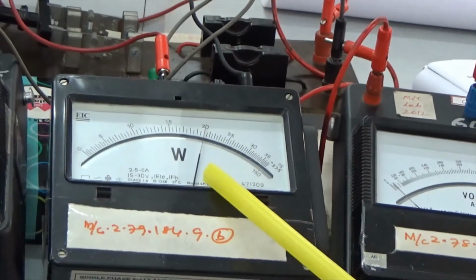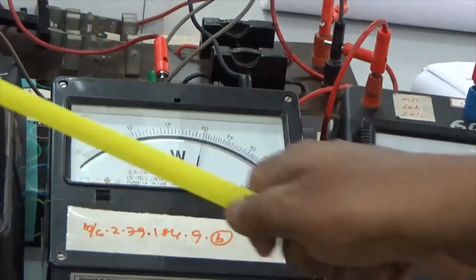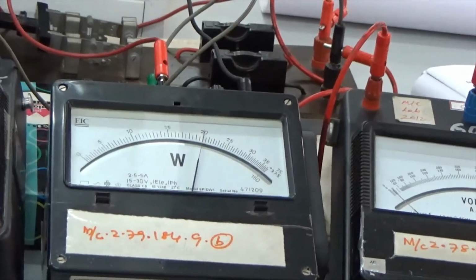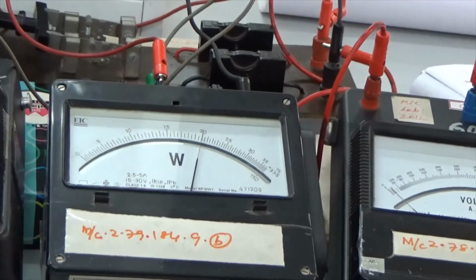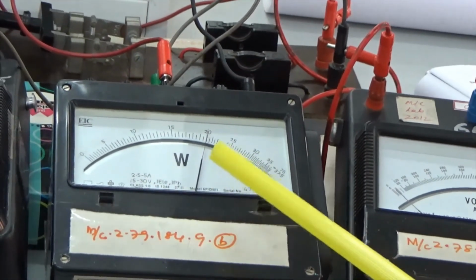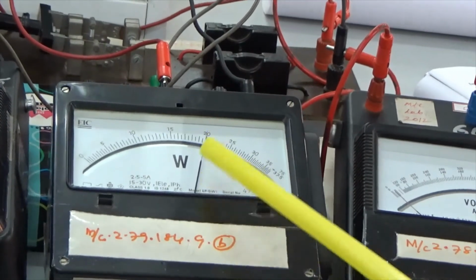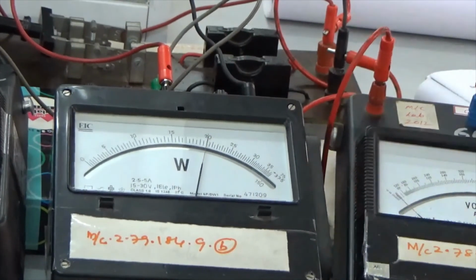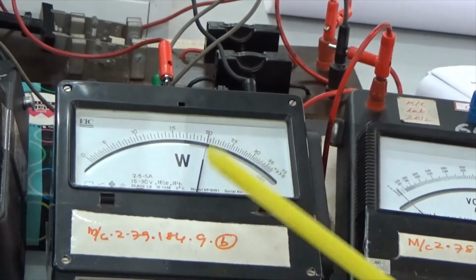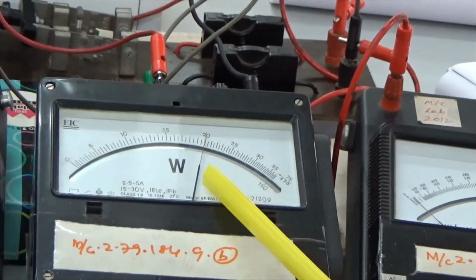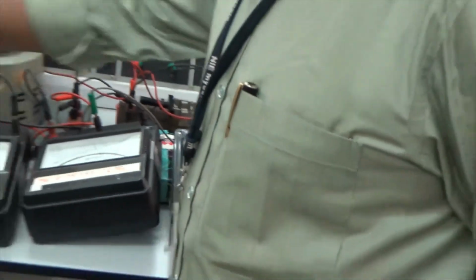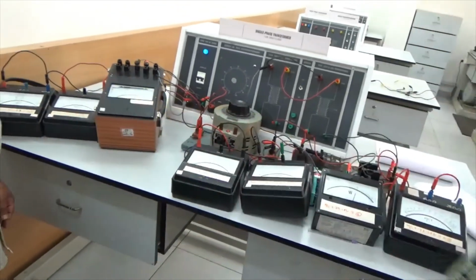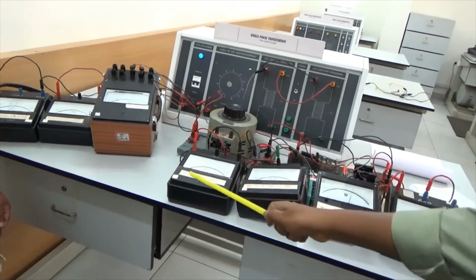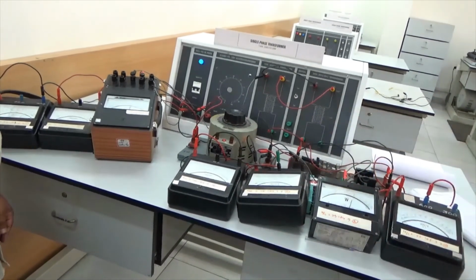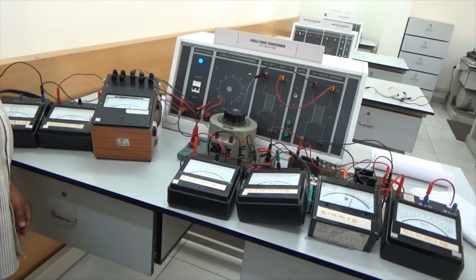This gives the copper losses, the I square R losses, that is the short circuit current squared times the resistance of the windings on the secondary side of the transformers. So this wattmeter gives the total copper losses in the set. If I want to calculate the efficiency of the individual transformer, then you have to divide this wattmeter reading by 2. The iron losses divided by 2 likewise give the individual iron losses. Once I know the iron losses and copper losses of the individual machine, it is easy to calculate its efficiency.